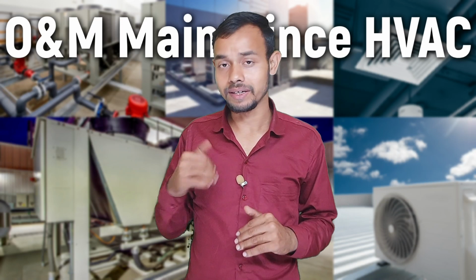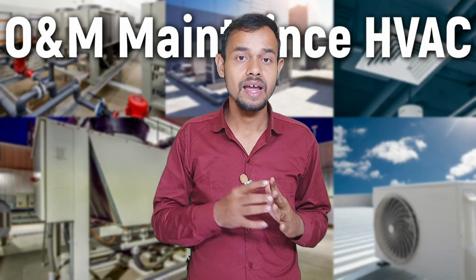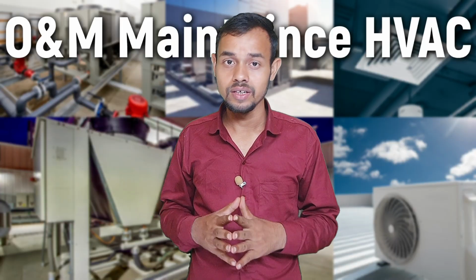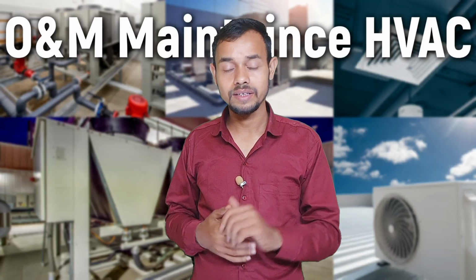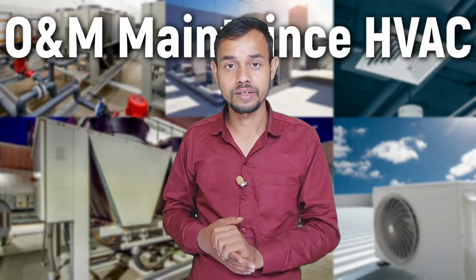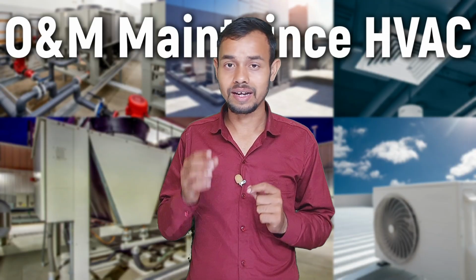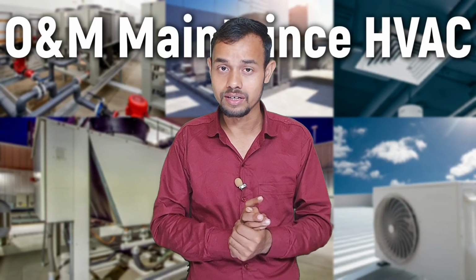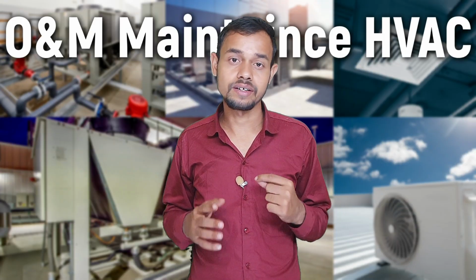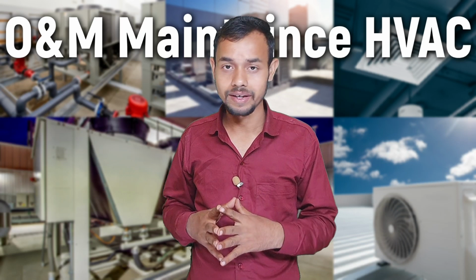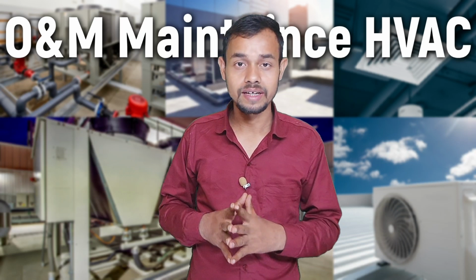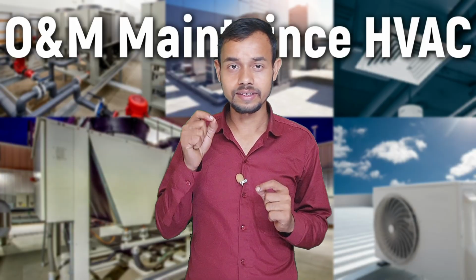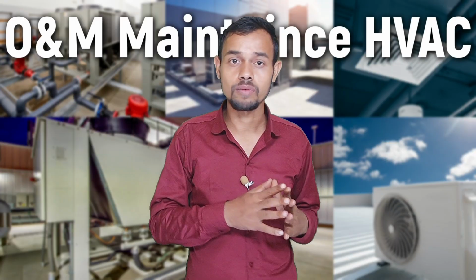This was operation activity. In maintenance activity you can do filter cleaning and replacement, coil washing, belt inspection and tensioning, lubrication, and pump alignment. And water treatment, like controlling pH, TDS, and hardness. And descaling heat exchangers, refrigerant level checking, drain line cleaning, motor megger testing, and VFD servicing. This is a normal day for an HVAC operation engineer.